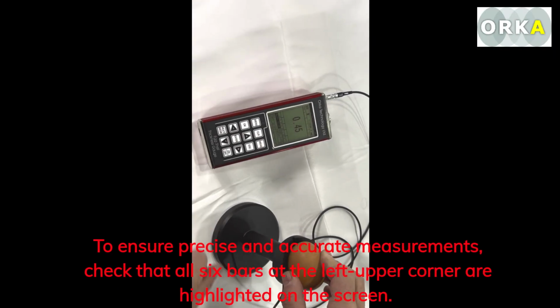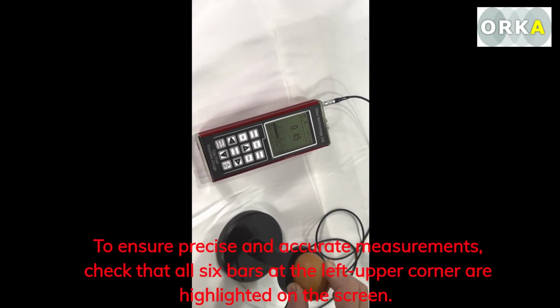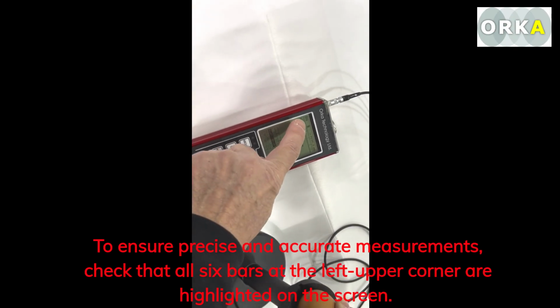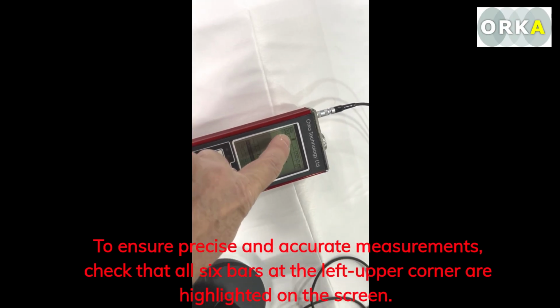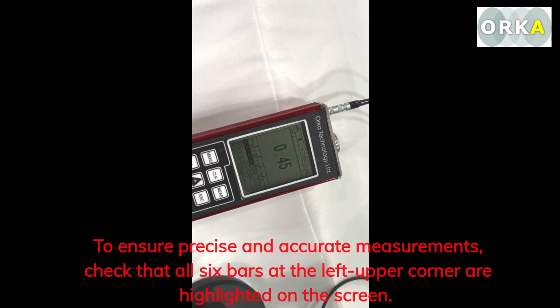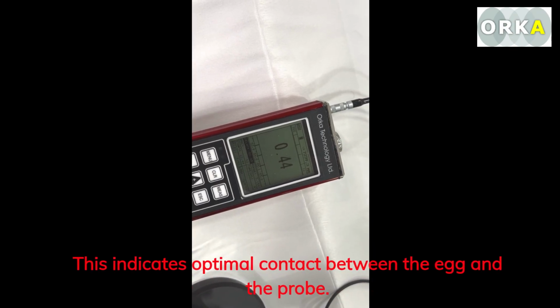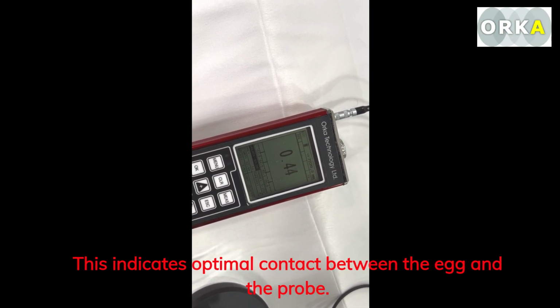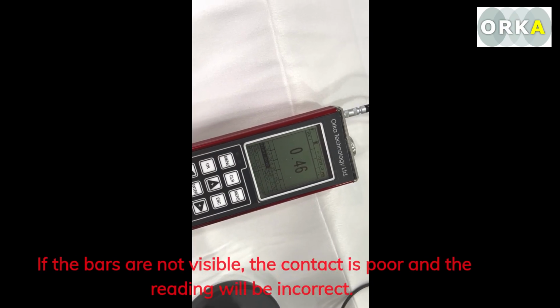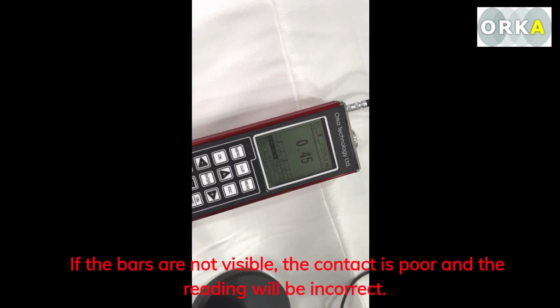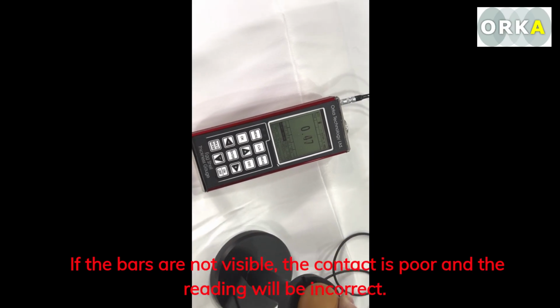To ensure precise and accurate measurements, check that all 6 bars at the left upper corner are highlighted on the screen. This indicates optimal contact between the egg and the probe. If the bars are not visible, the contact is poor and the reading will be incorrect.